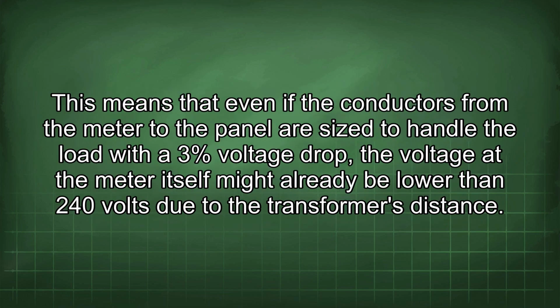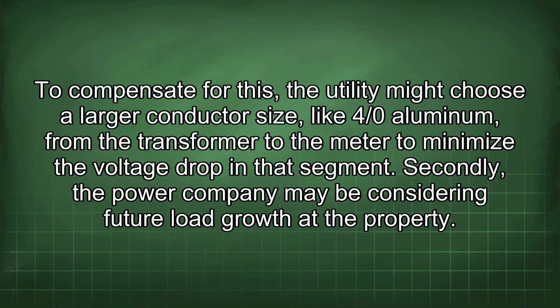This means that even if the conductors from the meter to the panel are sized to handle the load with a 3% voltage drop, the voltage at the meter itself might already be lower than 240 volts due to the transformer's distance. To compensate for this, the utility might choose a larger conductor size, like 4/0 aluminum, from the transformer to the meter to minimize the voltage drop in that segment.